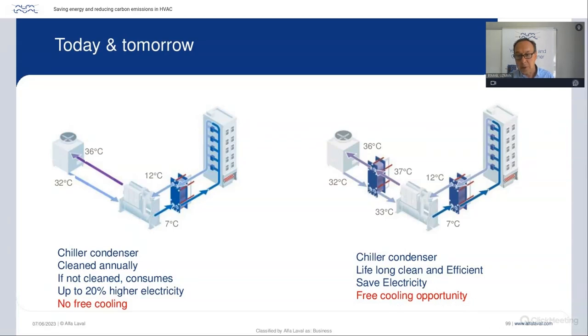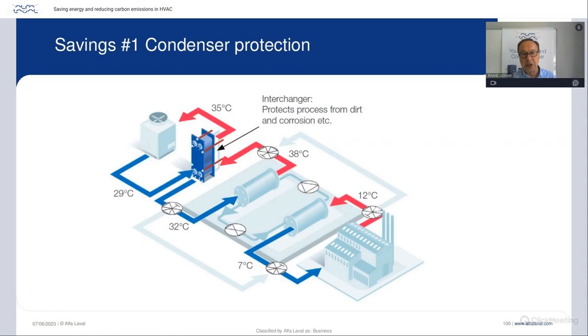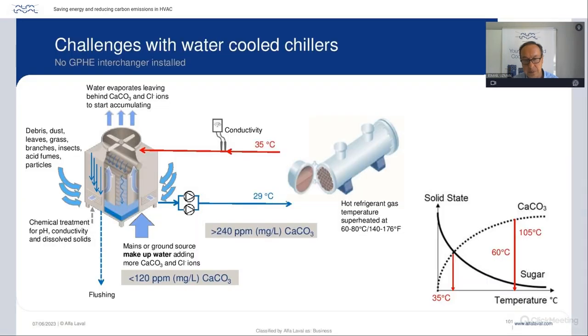Now, if we look a little bit deeper into this application, there is a double benefit of this heat exchanger. One is to protect the condenser. And you can see here that it is serving the condenser with the cooling tower water. Let's dig a little bit into this, and after that we look at pre-cooling with a case example as well.